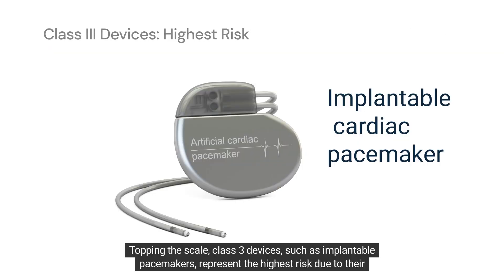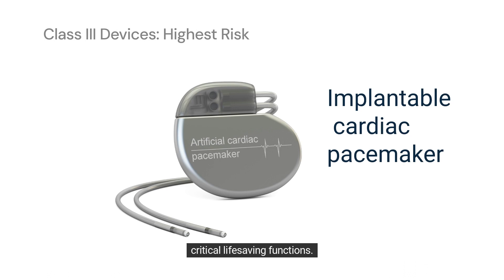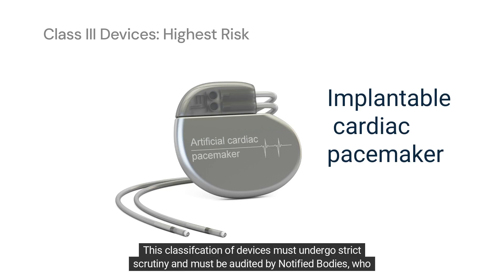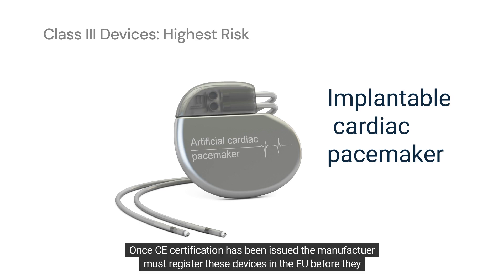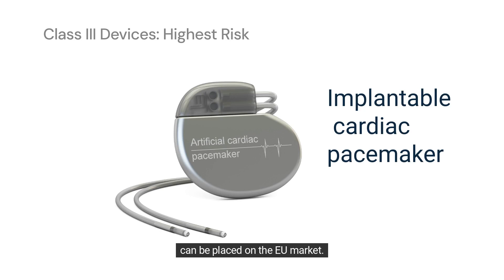Topping the scale, class 3, such as implantable pacemakers, represents the highest risk due to their critical life-saving functions. This classification of devices must undergo strict scrutiny and must be audited by notified bodies, who will assess the technical documentation and quality management documentation before CE certification can be issued. Once CE certification has been issued, the manufacturer must register these devices in the EU before they can be placed on the EU market.